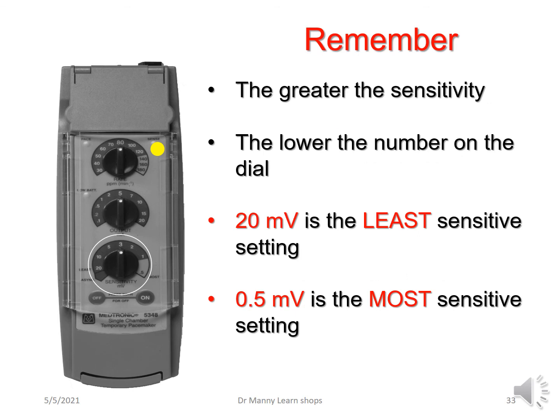Remember: the greater the sensitivity, the lower the number on the dial. 20 millivolts is the least sensitive setting — click it into asynchronous mode and there's no sensing. 0.5 millivolts is the most sensitive setting. So 0.5 is not the least — it's the most sensitive. And 20 millivolts is not the most sensitive — it is the least sensitive.